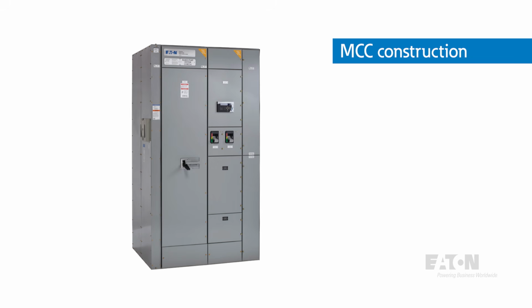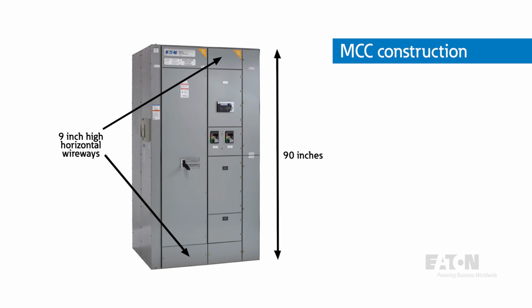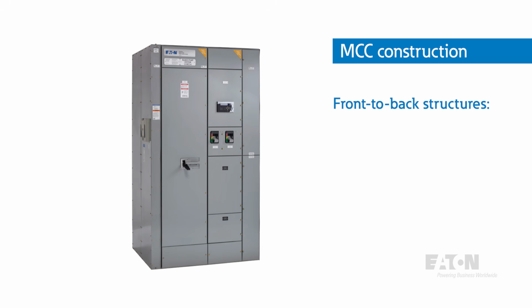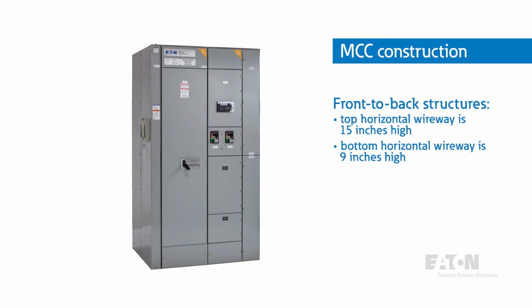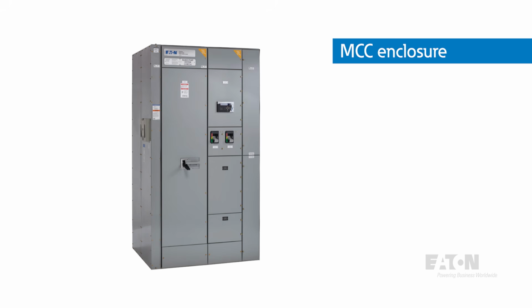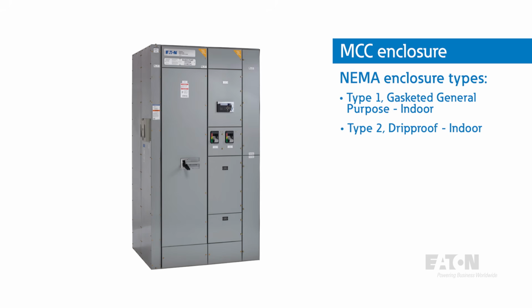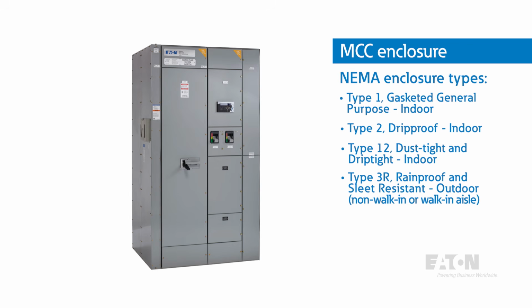The typical height of an MCC structure is 90 inches, with 9-inch horizontal wireways at the top and bottom for wiring. The remaining 72 inches are used for mounting control units, which can be arranged in various configurations and sizes. For front to back structures, the top horizontal wireway is 15 inches high and the bottom is 9 inches, providing 66 inches of usable space in the rear. MCC enclosures come in various types, including NEMA Type 1, 2, 12, and 3R. Type 3R enclosures can be non-walk-in or walk-in aisle.